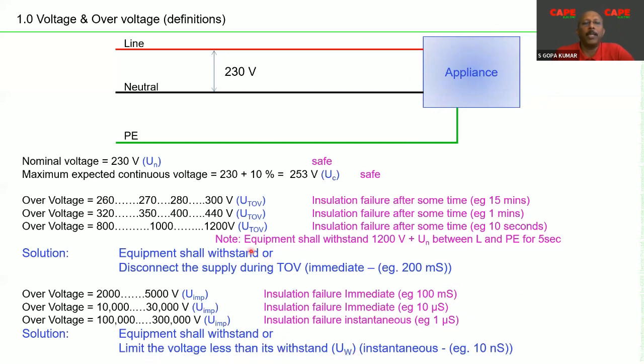Very important. See, in the previous case, the time is more. You have time to disconnect. Whereas in the second case, transient overvoltage, you don't have enough time to disconnect, because for disconnection, you need some device to operate. Before the disconnection happens, the withstanding time is quite less. So the technique to be applied is, limit the voltage.